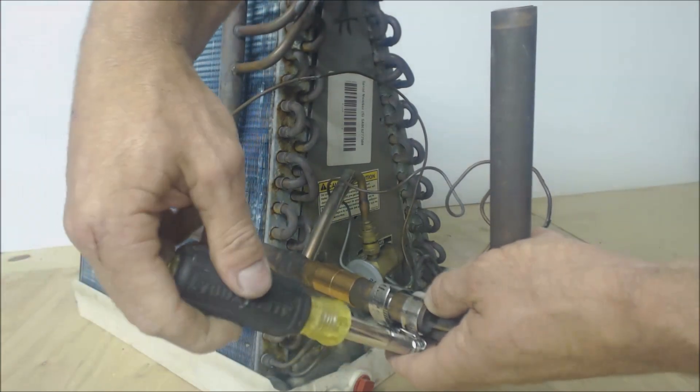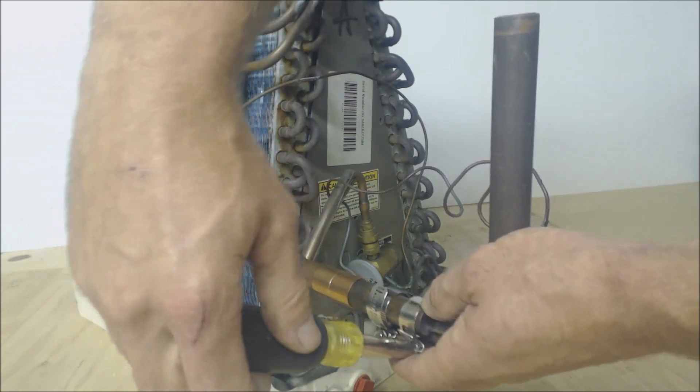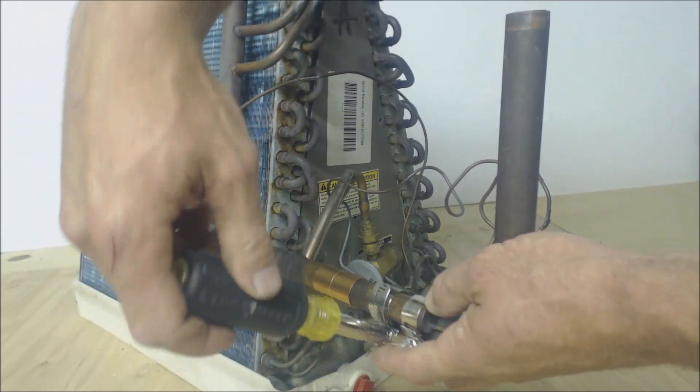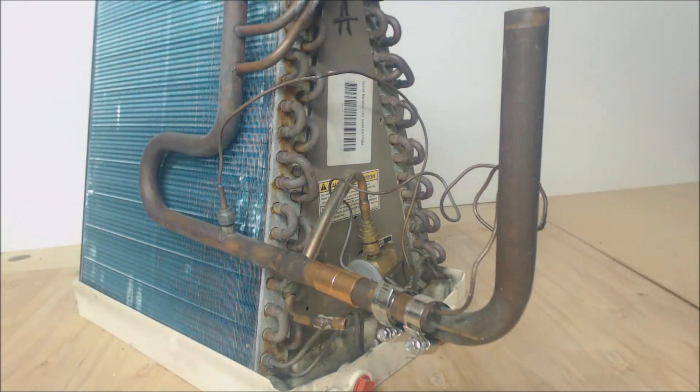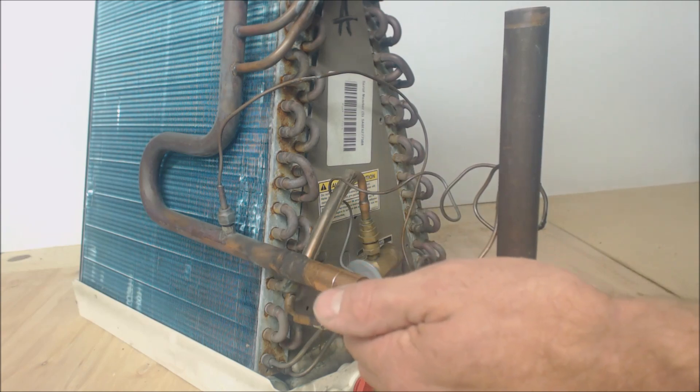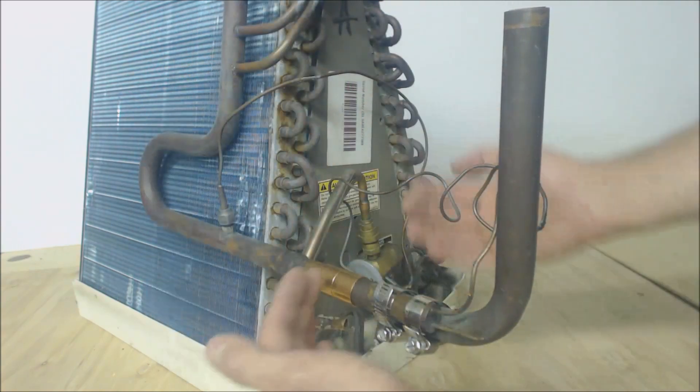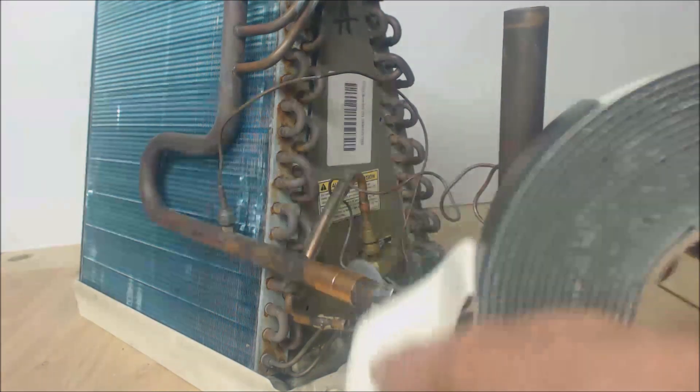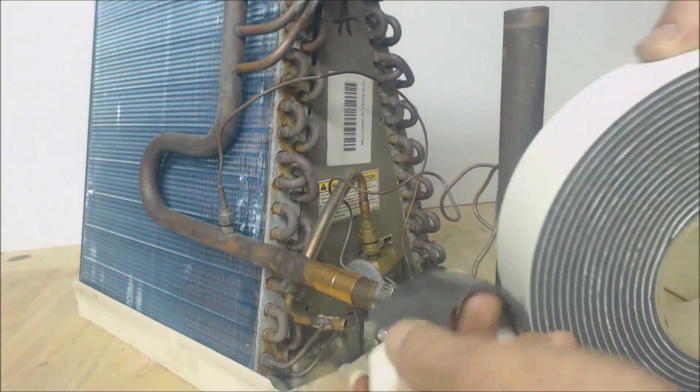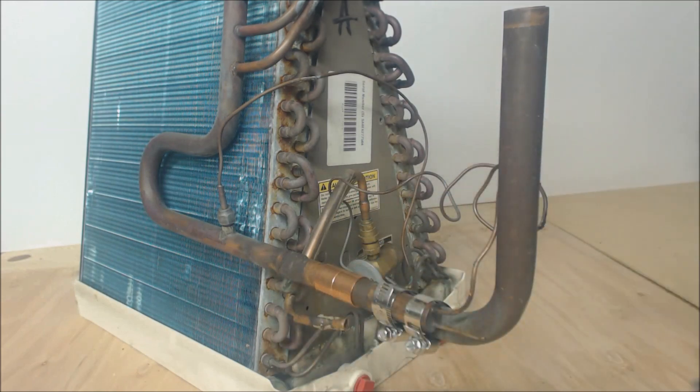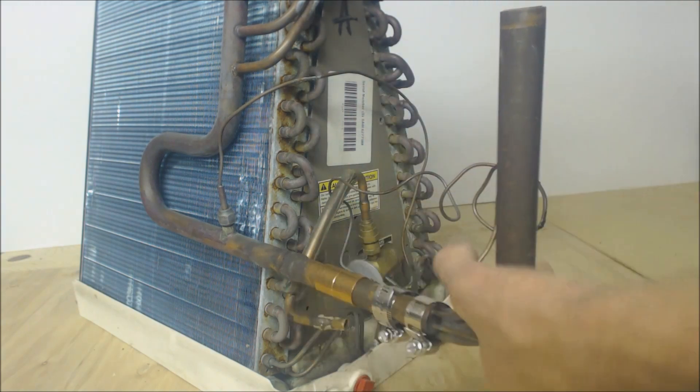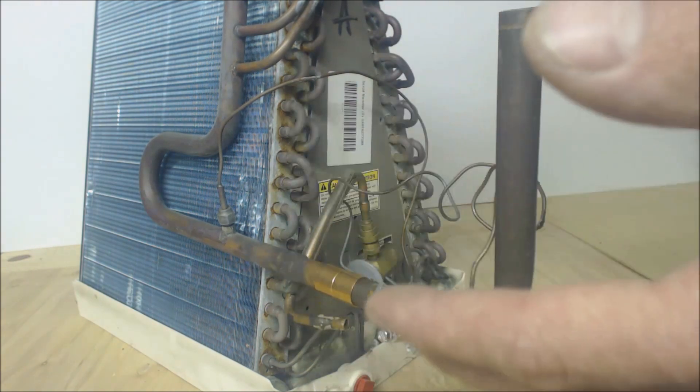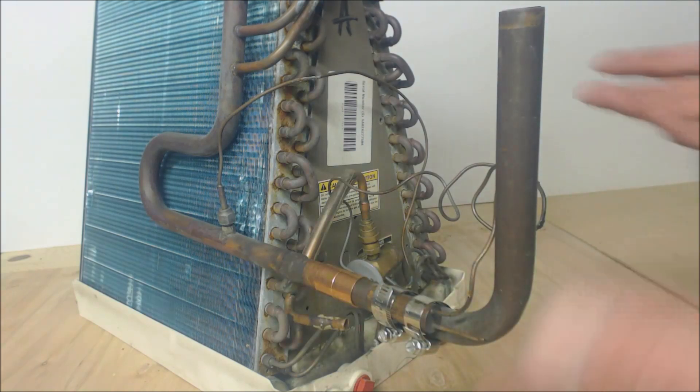Most manufacturers might say 10 to 2, so that's where we're putting it, right about 10 o'clock. Tighten up a little at a time. Especially when the TXV bulb is installed outside of the coil box, you want to use some foam tape on it - some sticky foam tape. Or you can wrap the Armaflex that's typically around here over top of this and zip tie it on, making sure it's completely tight so it's not sensing the conditioned air within the house or building.